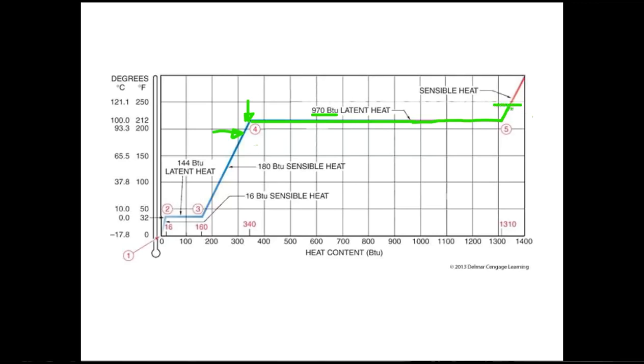At that point, it hits the compressor, it gets compressed, and the first part of the condensing coil desuperheats, removes the heat. We hit the saturation point. It comes back down as it condenses back down from the saturation point into 100% liquid, goes through the evaporator, or the condenser, excuse me, and it becomes subcooled liquid again. Then it hits the metering device, goes back through the evaporator coil, and that is our refrigeration cycle.